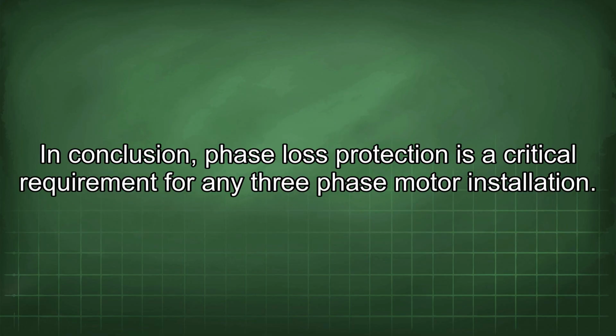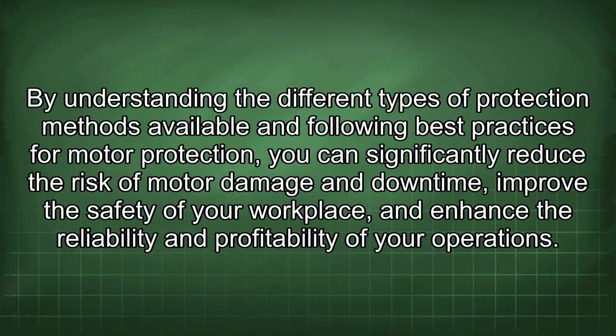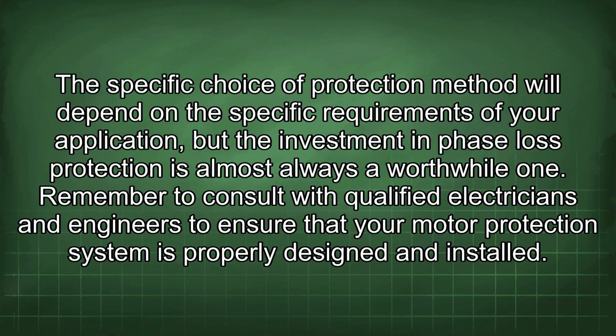In conclusion, phase loss protection is a critical requirement for any three-phase motor installation. By understanding the different types of protection methods available and following best practices for motor protection, you can significantly reduce the risk of motor damage and downtime, improve the safety of your workplace, and enhance the reliability and profitability of your operations. The specific choice of protection method will depend on the specific requirements of your application, but the investment in phase loss protection is almost always a worthwhile one. Remember to consult with qualified electricians and engineers to ensure that your motor protection system is properly designed and installed.